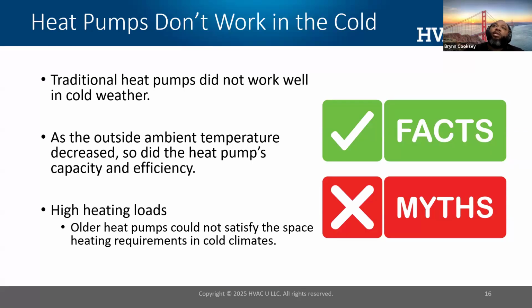Another myth that we get into is that heat pumps don't work in cold climates. And that's also a myth. The traditional heat pumps, the heat pumps from yesteryear, did have challenges operating in cold climates. Hence, that's why they were used in the warmer parts of the United States. As outside temperature drops, for older heat pumps before cold climate technology, heat pump capacity and efficiency dropped off with it. So it really didn't see rapid market adoption in the northern part of the country.